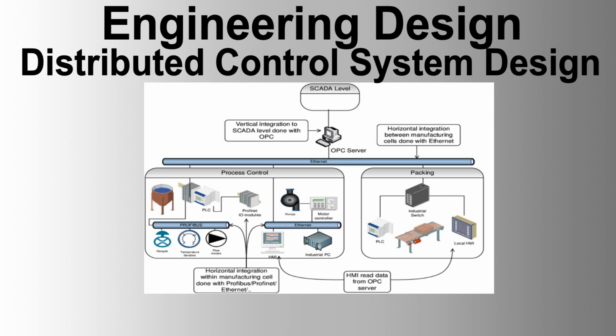Distributed Control System. Deliverables. The DCS vendor's scope of work includes the following activities: design, program, manufacture, supply, testing, installation, and commissioning of DCS equipment and integration with the existing control system. Programming must align with provided functional specifications. Any deviations must be communicated before implementation. Graphics generation, including all the packages serially connected to the DCS system. Configuration related to sequence of event timestamped points and diagnostic tags for both DCS and related systems.